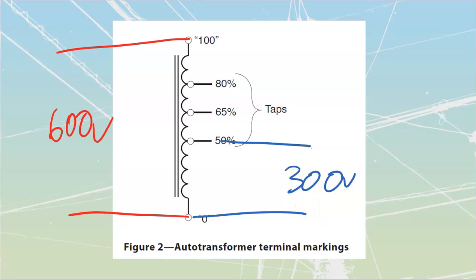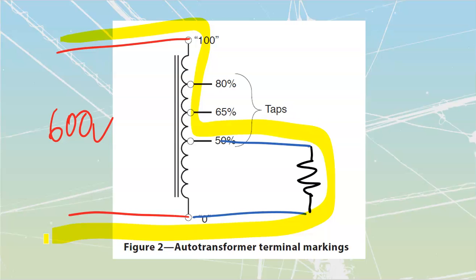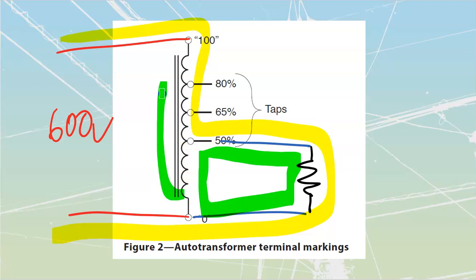Some of our currents, if we refer back to autotransformers, and if I put this here as being a load, let me just quickly do that so that we're familiar with our current path. If I've got a load connected across here, I'm going to have 2 current paths that flow. One of those current paths is going to be through like that, where some is directly transmitted to the load through this set of windings over here. I'm also going to have another set of current that flows through here, which gives me flux that links through from the other side. Once again, if you're unfamiliar with your autotransformers, you shouldn't be. You're in 3rd year, and you've got your 2nd year materials. Go back and take a look through your autotransformers and then maybe come back and take a look at the rest of these.